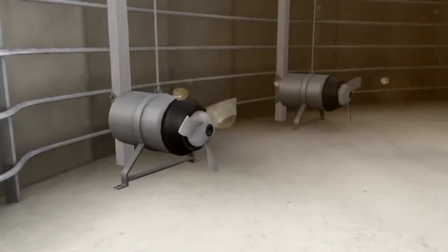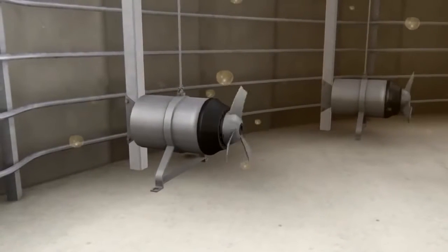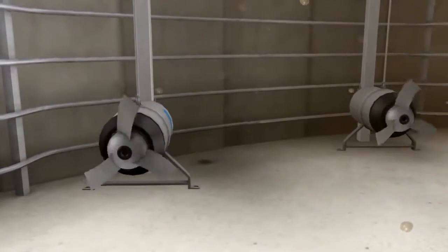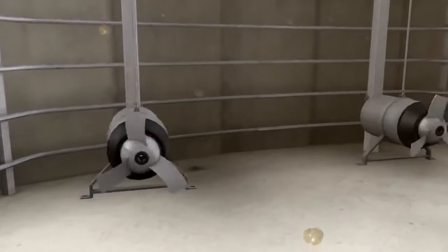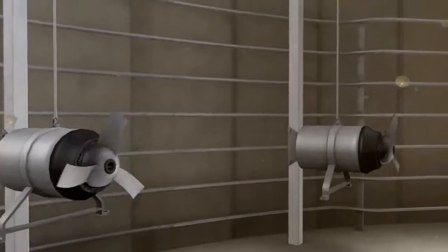Submerged, height-adjustable agitators ensure an even substrate and heat distribution in the fermenter. They guarantee the complete and thorough mixing of the mass. Since the agitators are attached by a cable suspension and are not built in, cleaning and maintenance are possible while the plant is running.